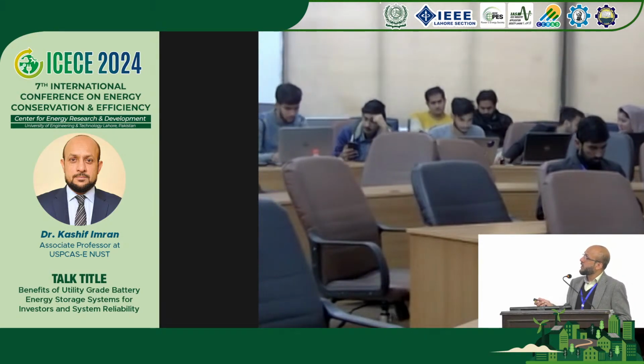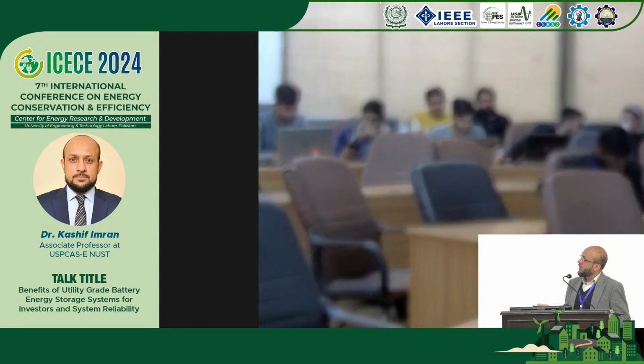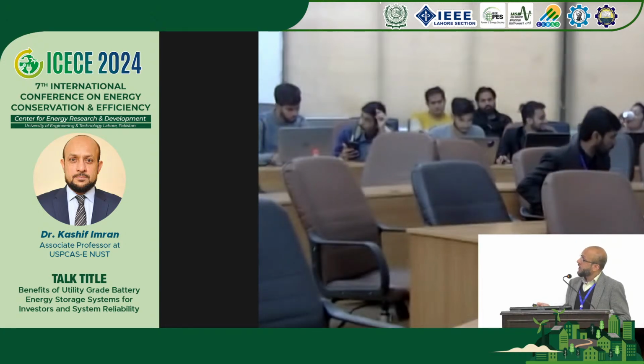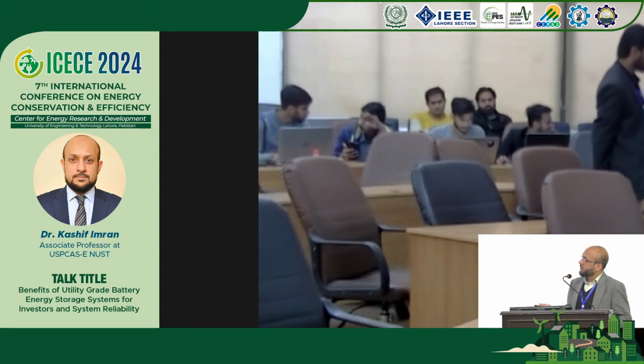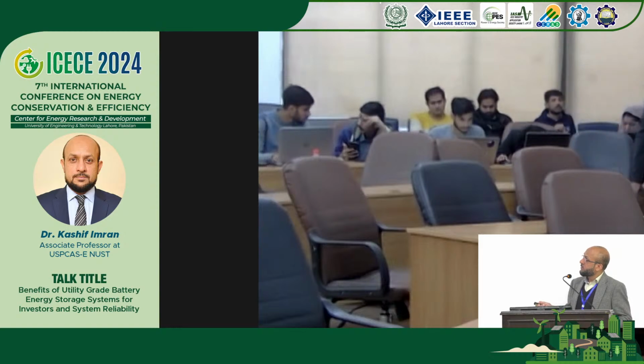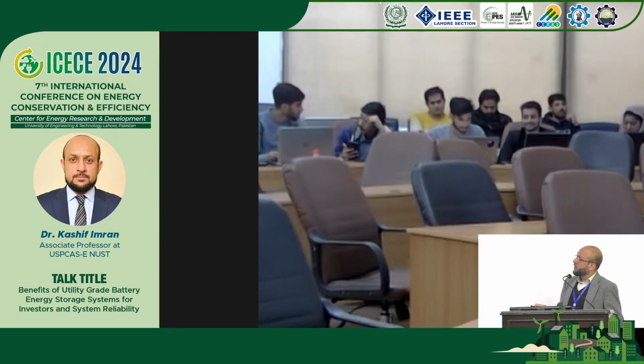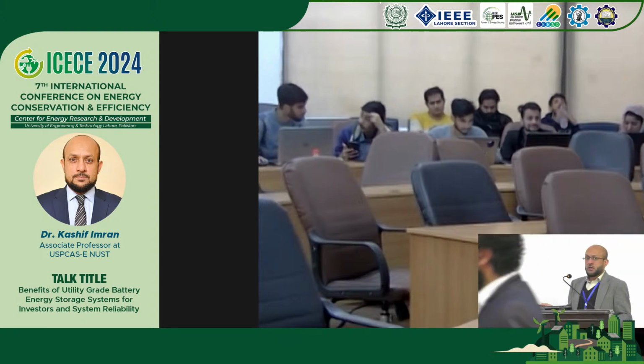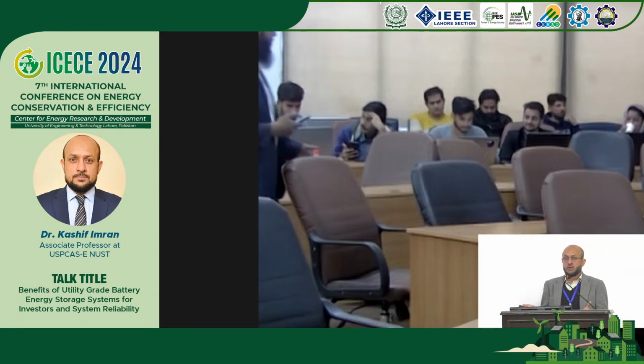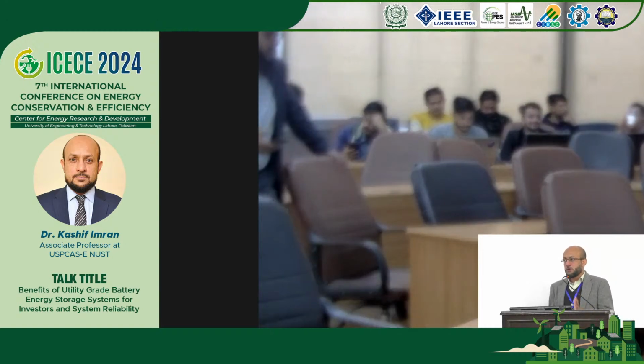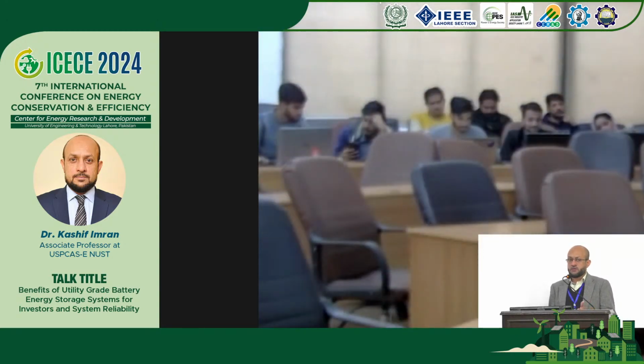But now we can have a loss factor, where loss factor LB is calculated by expected unserved energy multiplied by number of days per year, multiplied by number of years, multiplied by value of lost load. So that's how we use two reliability indices, expected unserved energy and value of lost load, together to quantify the impact of battery on a system.